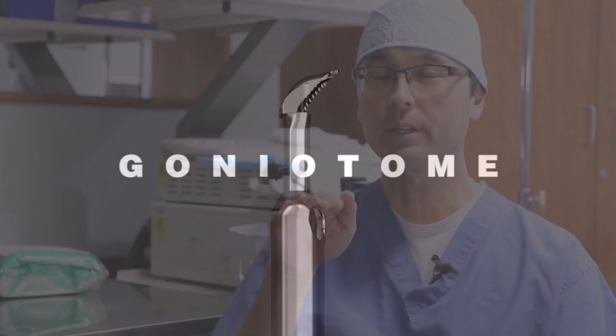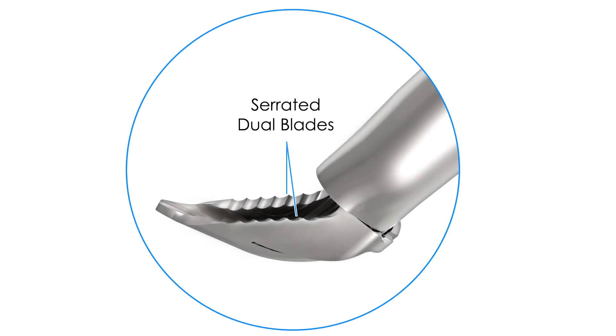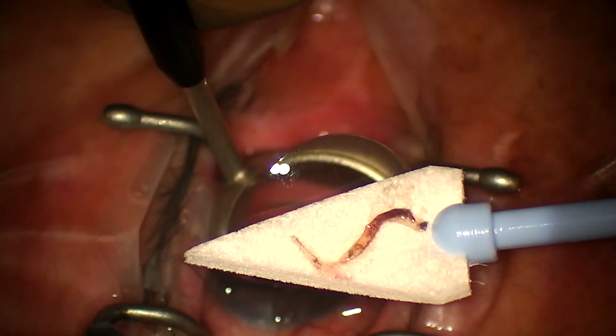In other words, through a clear corneal incision, the instrument is able to remove a strip of the trabecular meshwork and inner wall of Schlemm's canal. By doing that, it therefore increases the aqueous outflow through the trabecular outflow pathway. The goniotome is a device with a double-edged blade with serrations and a sharp tip. The tip is designed to advance across the anterior chamber, insert through the trabecular meshwork into Schlemm's canal. And then as you advance the device across the trabecular meshwork and Schlemm's canal, it lifts the trabecular meshwork, puts it on tension, and then cuts the two ends of the trabecular meshwork, thereby removing a strip of the tissue.